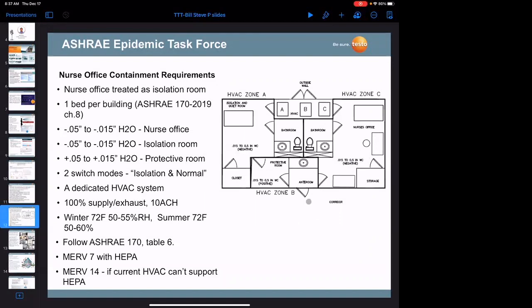You've got exhaust fans, new supply fans, interlocked basic controls, because you have to have 2 switchable modes of operation between isolation and normal mode, being unoccupied, no student in this infected area, and the nurse is just at her desk. It's got to be 100% supply and exhaust, just like a laboratory building with 10 air changes per hour. And you've got to have at least a MERV 14 filter if it can't support a HEPA filtration system, or a MERV 7 with HEPA.